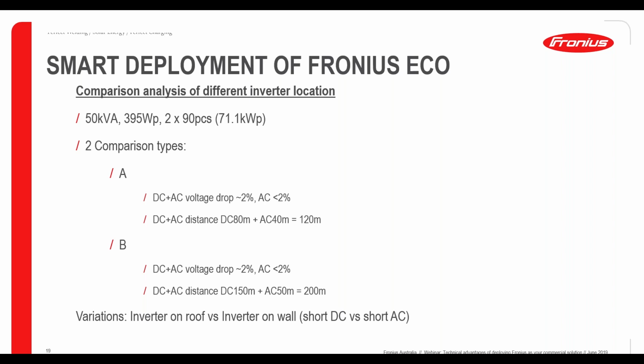Typically what we've tried to do, as listed here, is use a small to medium commercial system compared to using 2 inverters of ours and 1 competitor. This will become obvious in the slide coming next. What I wanted to highlight here is that we've tried to run 2 typical comparisons, A and B. A would typically be a shorter option, if you will, so shorter DC and shorter AC runs. B would be a typical longer one.